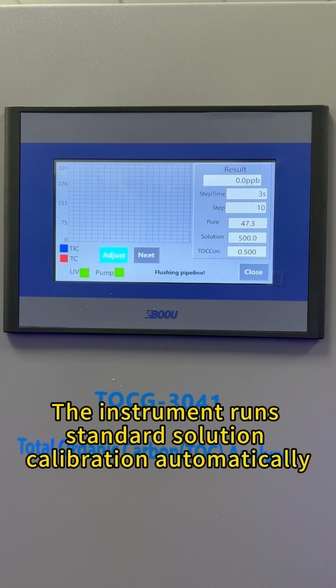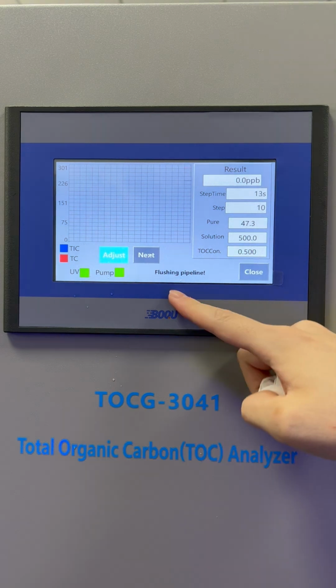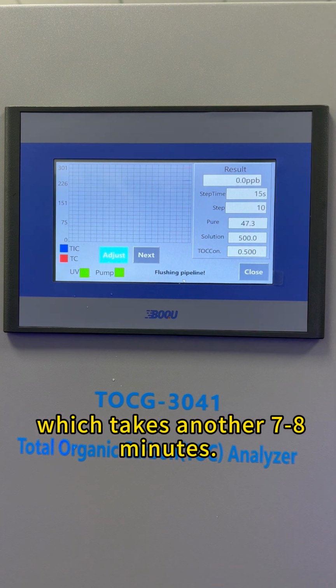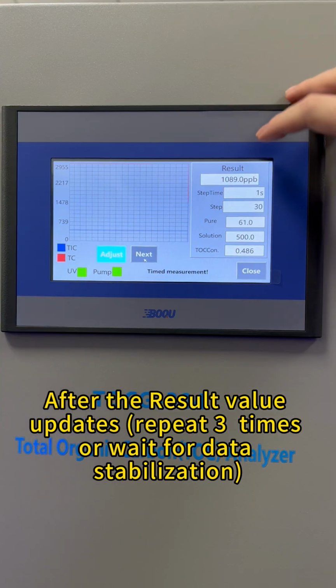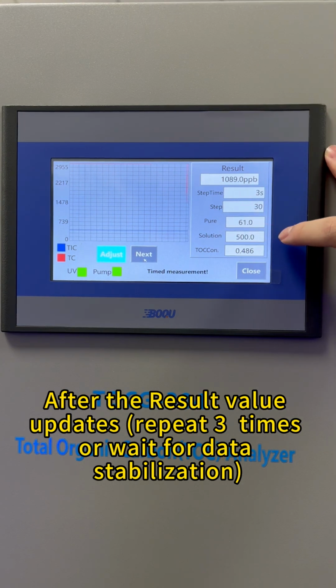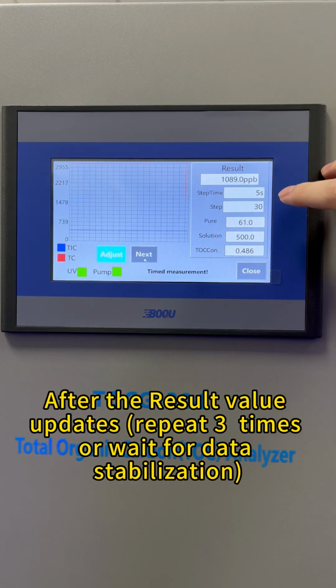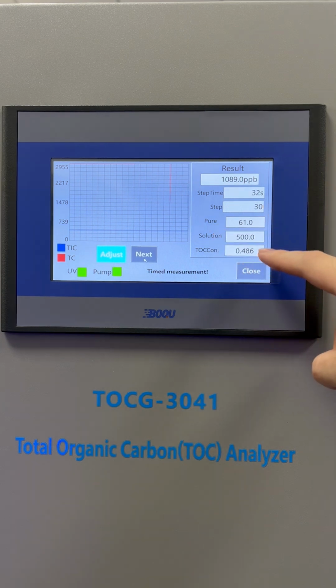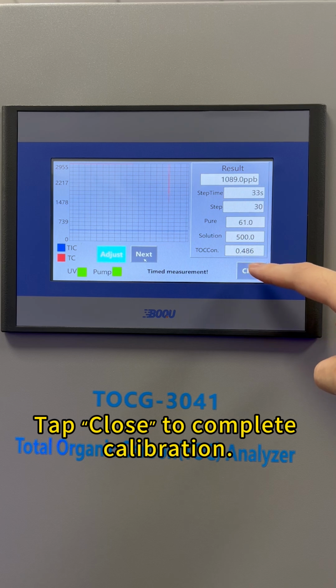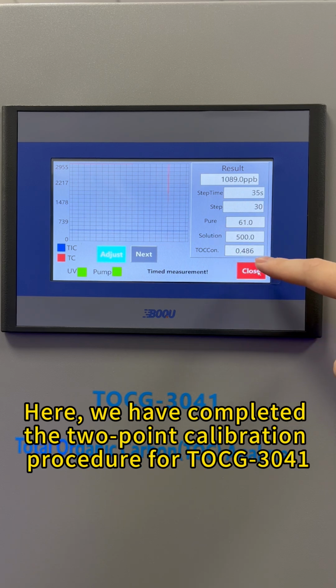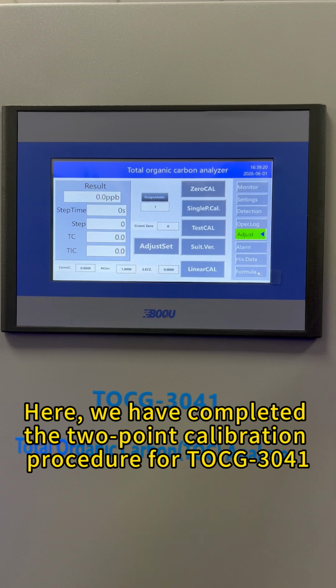The instrument runs standard solution calibration automatically, which takes another 7 to 8 minutes. After the result value updates, repeat 3 times or wait for data stabilization. Tap Close to complete calibration. Here, we have completed the 2-point calibration procedure for TOCG-3041.